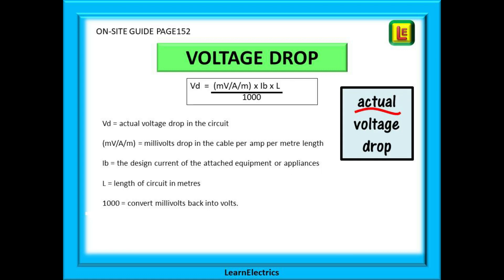Now we can look at the actual volts drop and compare this to the maximum permitted values. The very simple formula is shown here. VD is the actual volts drop in the circuit. And this funny symbol MVAM is the millivolts drop in the cable for every amp of current flowing through every meter of the circuit. IB is the design current of the attached equipment or appliances. How much current has the manufacturer designed it to use. And L is the length of the circuit in meters.